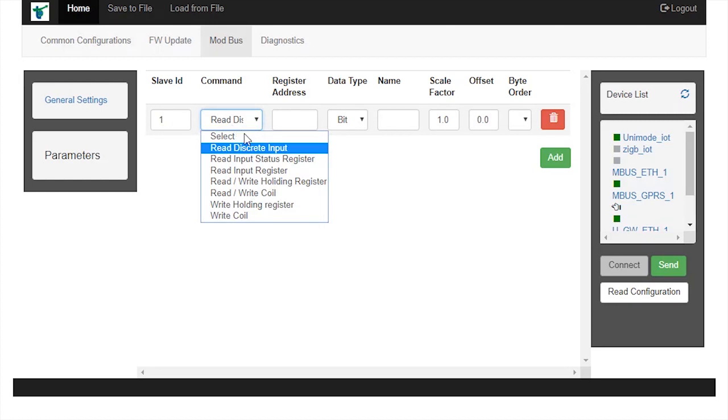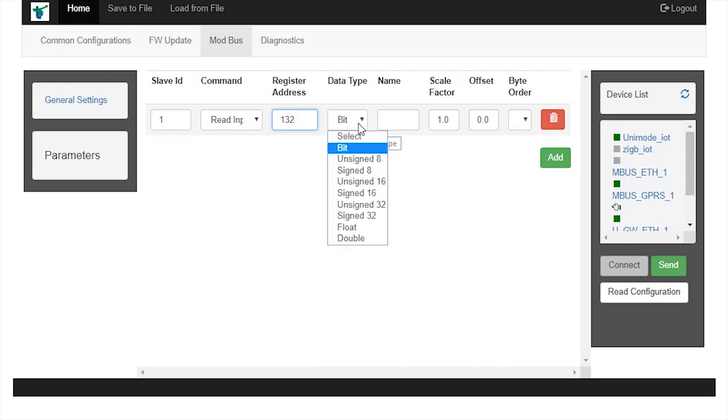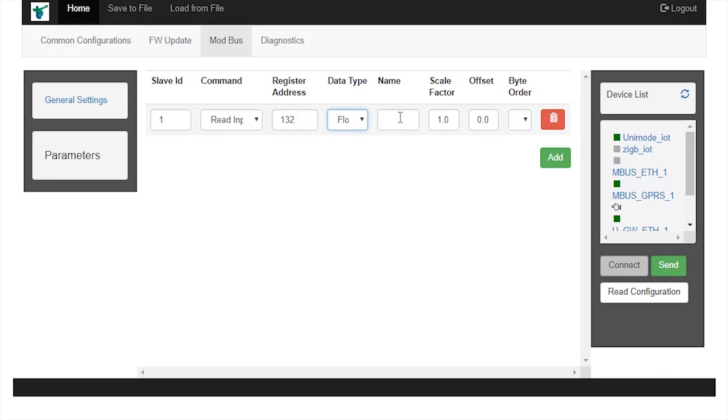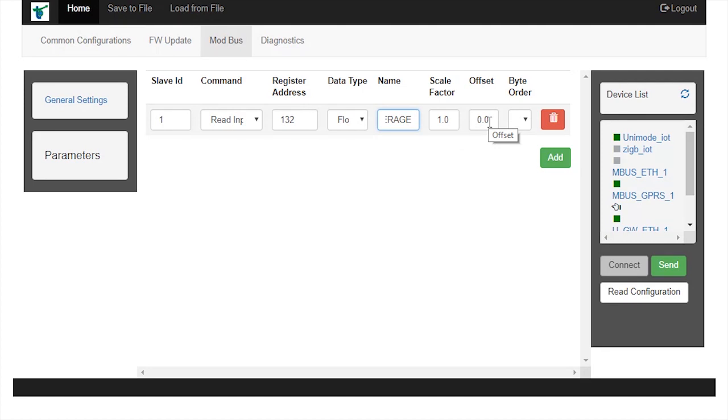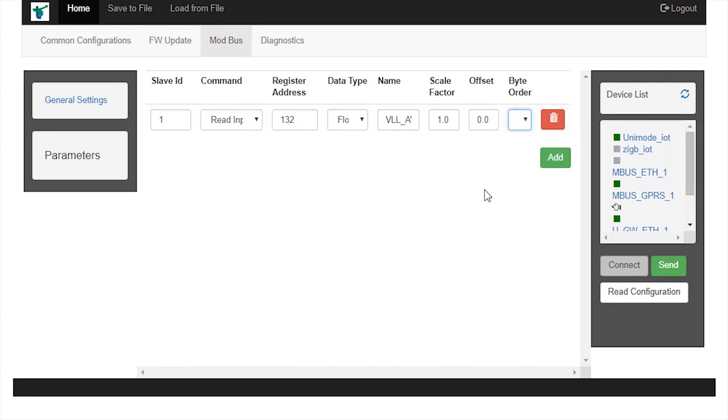Command as read input register, register address as 132, data type as float, name as vll_average, scale factor 1.0, offset 0, and byte order as cd_ab.